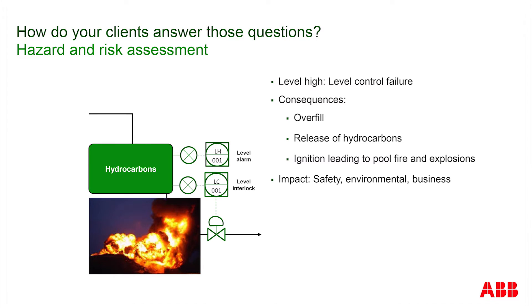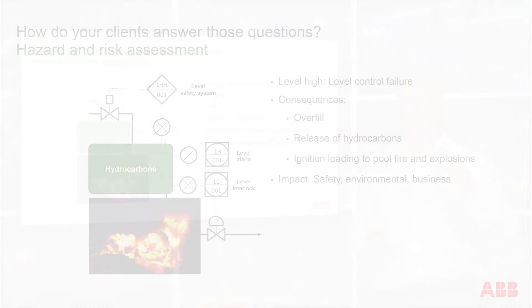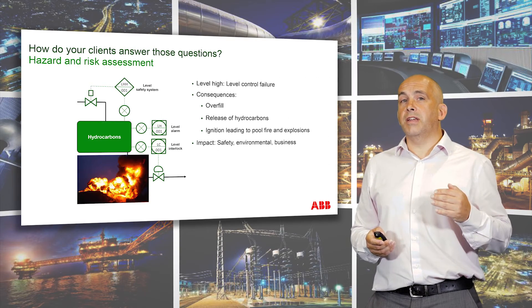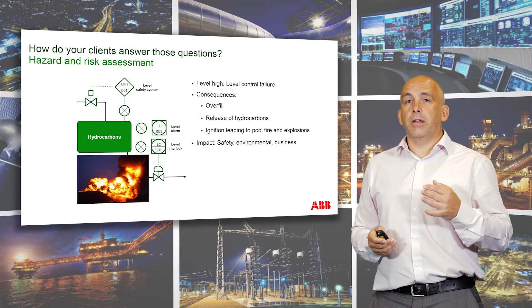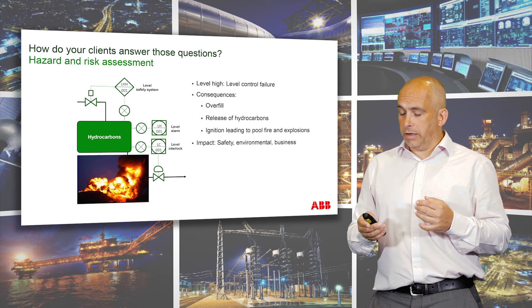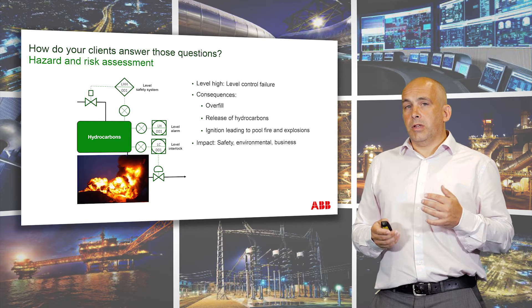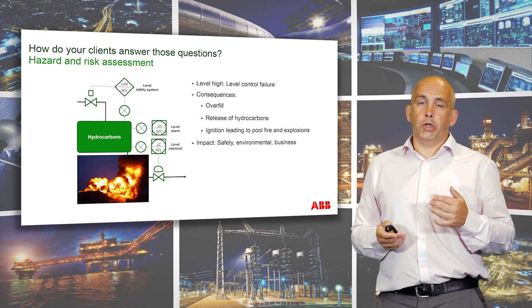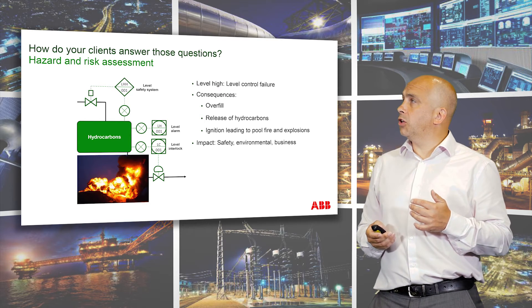Another barrier could be a high level alarm. So when the level gets high in that vessel, the alarm sounds in the control room. And finally, we have a safety instrumented function. So when the level gets ultra high, it closes the feed into that vessel and the level can't get any higher. So that's how our customers answer the first two questions.